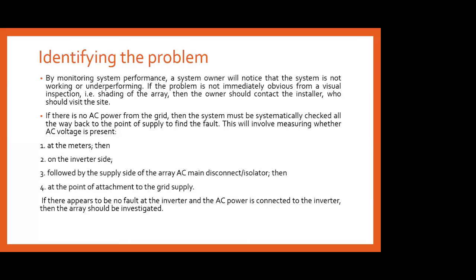Yes. The first thing, if there is no AC power from the grid itself, then the system must be systematically checked all the way back to the point of supply to find the fault. And of course, this involves measuring whether AC voltage is present or not. How to check whether the AC voltage is present or not? We have to check at the meters on the inverter side, followed by the supply side of the array, the AC main disconnector isolator, then at the point of attachment to the grid supply. So if there is no AC power from the grid, we have to check all those things starting from the meters, then the inverters, then the supply side of the array, AC mains, then the point of attachment to the grid supply.